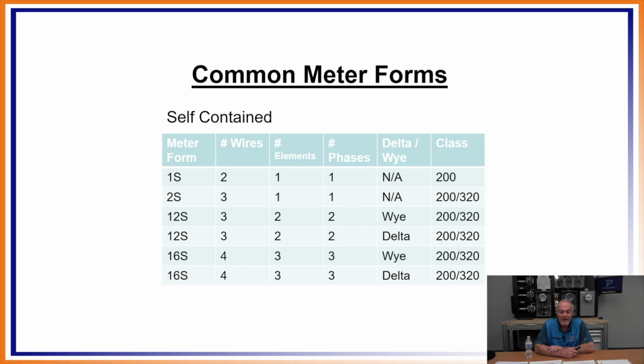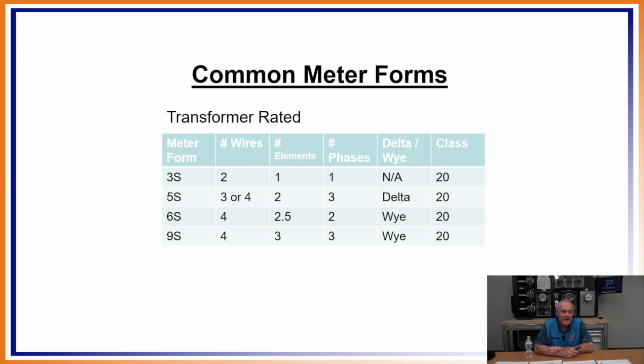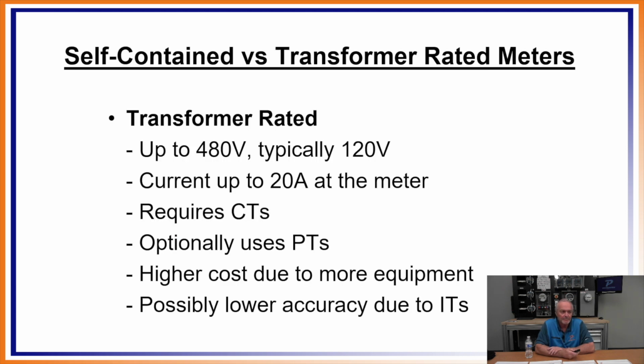Over on the far right-hand side, when we start designing the site and making our choices of meters, how much current they can handle is going to be one of the critical criteria. Then we get to the transformer rated: we've got a 3S for the single phase, and 5S, 6S, 9S. In there the class says 20, but remember that's just the meter. You're going to have external CTs and PTs, which bring it down so that the meter is only seeing 20 amps. But the actual service can be a lot larger than that, so we can just upsize the CTs.